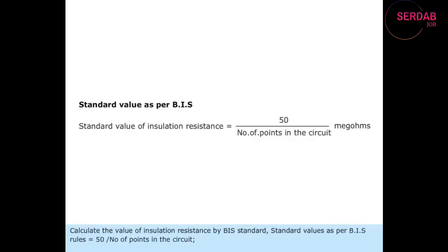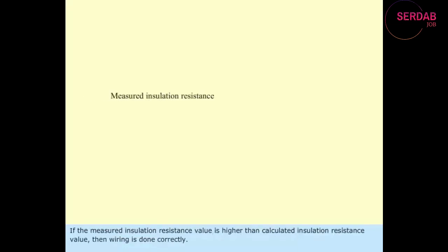Calculate the value of insulation resistance by BIS standard. Standard values as per BIS rules equals 50 over the number of points in the circuit. In case of wiring done in PVC insulated cable, 50 is replaced by 12.5. If the measured insulation resistance value is higher than calculated insulation resistance value, then wiring is done correctly.